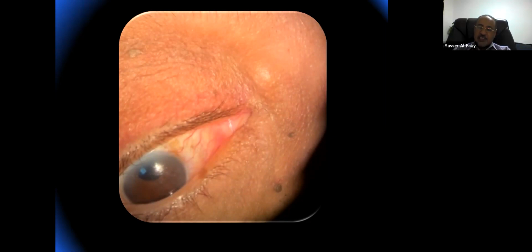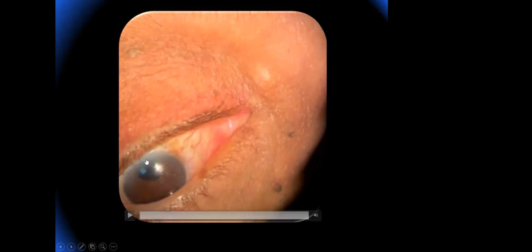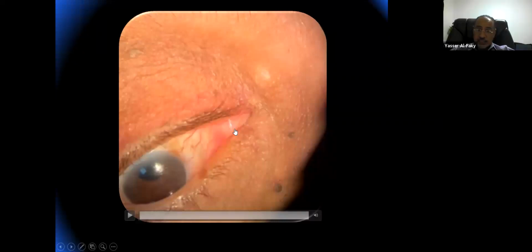Okay. Prof, I have a question. If you want to remove it, is there a specific way to remove it, or just cut it and pull it? You have to rotate it again, so you will have the top end in front of you, and then cut in between the stent while holding the stent with the suture inside and pull it out. Okay, so the suture should be inside the stent, so as not to damage the system. Don't cut the stent itself.